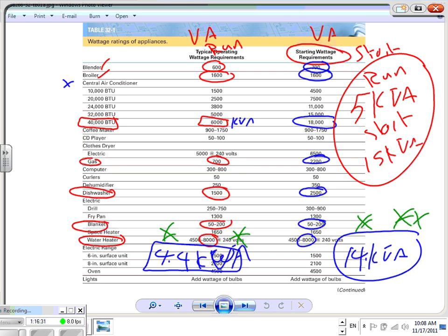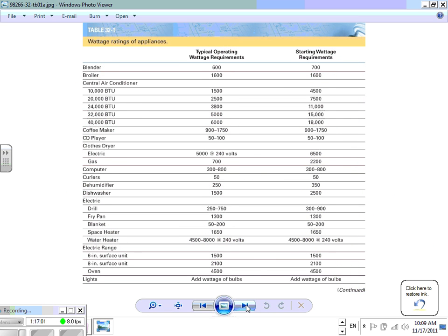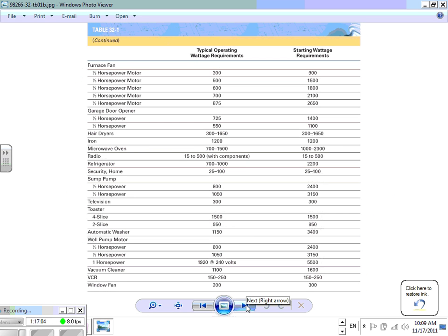Who cares? The question is, who cares, Chad? A cheaper, smaller-size motor, cheaper equipment. So I want you guys to highlight this one. And remember, next quarter when we size the generator, you have full control over the starting current by starting them in sequence, not at the same time. Make sense? So that's your capability. This is a good guide, Ashley, for residential, obviously. If you size a generator, you pick the loads that you have here, add them up, and that will give you the size of your generator.